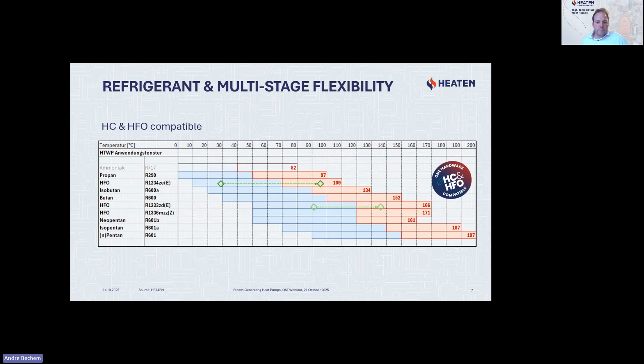But from the technology and hardware point of view, it's fairly simple to switch over from HFOs to hydrocarbons. The piston compressor, with its variable compression ratio, doesn't care too much about the different evaporation curve. Of course, a few seals and so on need to be exchanged, but the hardware is in general prepared for using both HFOs and hydrocarbons.